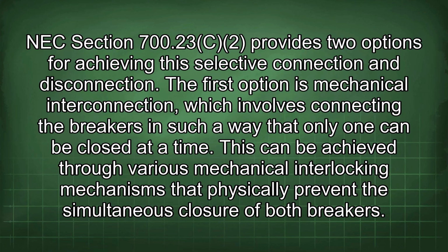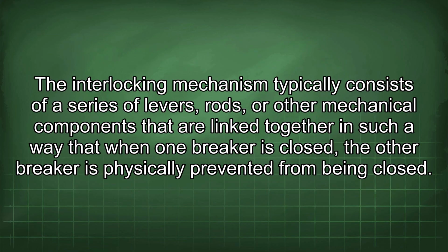700.23(C)(2) provides two options for achieving this selective connection and disconnection. The first option is mechanical interconnection, which involves connecting the breakers in such a way that only one can be closed at a time. This can be achieved through various mechanical interlocking mechanisms that physically prevent the simultaneous closure of both breakers. The interlocking mechanism typically consists of a series of levers, rods, or other mechanical components that are linked together in such a way that when one breaker is closed, the other breaker is physically prevented from being closed.